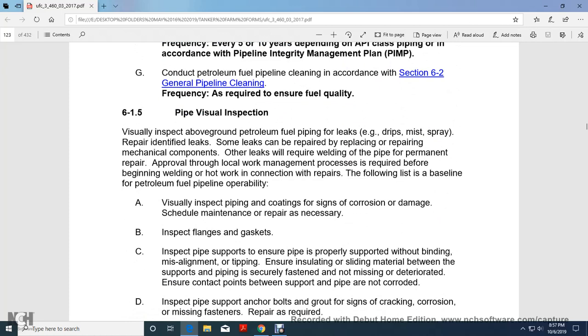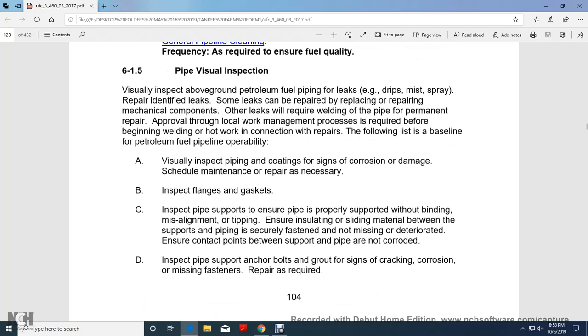Pipeline visual inspection, 6-1.5. Visually inspect above ground fuel piping for leaks, drips, emissions, and stains, with repair and identification of leaks. Some leaks can be repaired by replacing or repairing mechanical parts. Other leaks will require welding of the pipe for a permanent repair. All approval of the local work management process is required before beginning welding or hot work in connection with the repair. Following this, the listed items are the baseline for petroleum fuel pipeline operability.